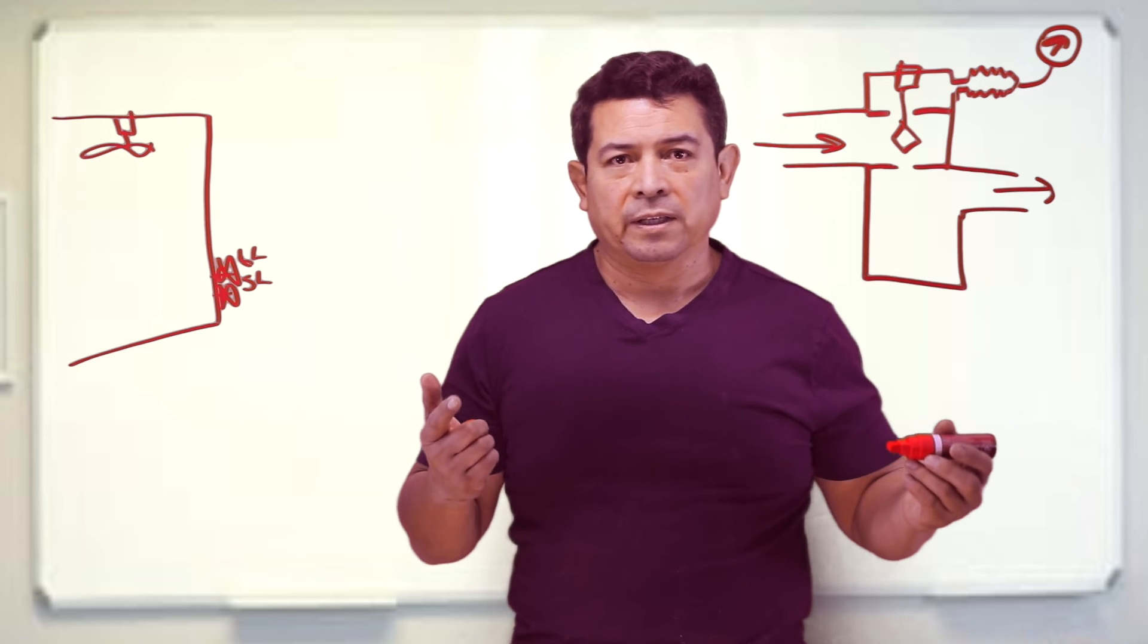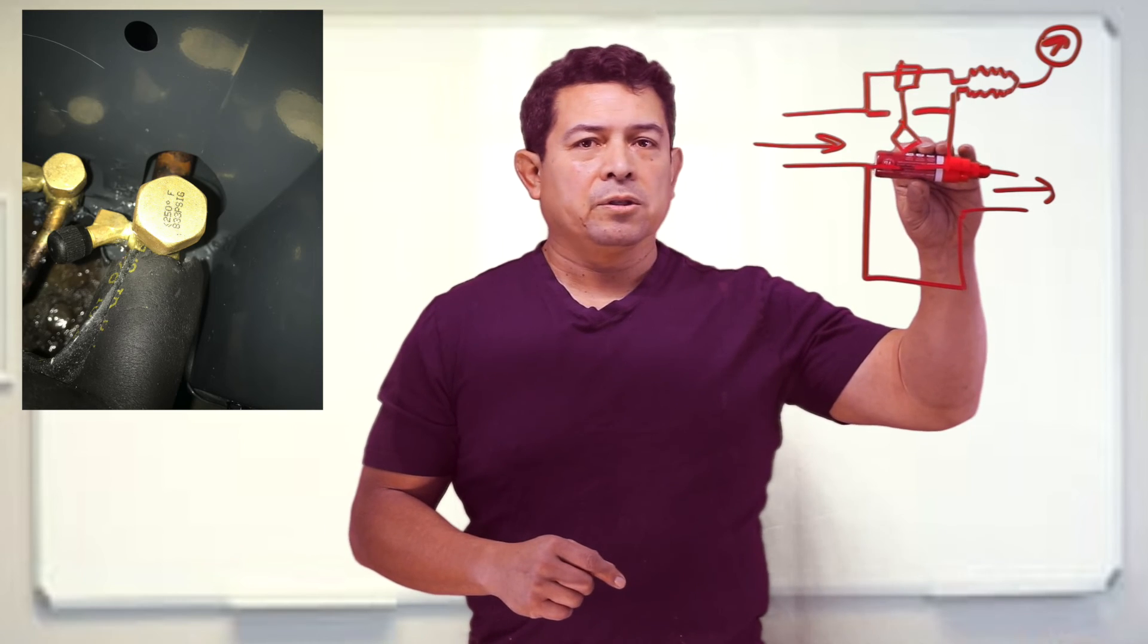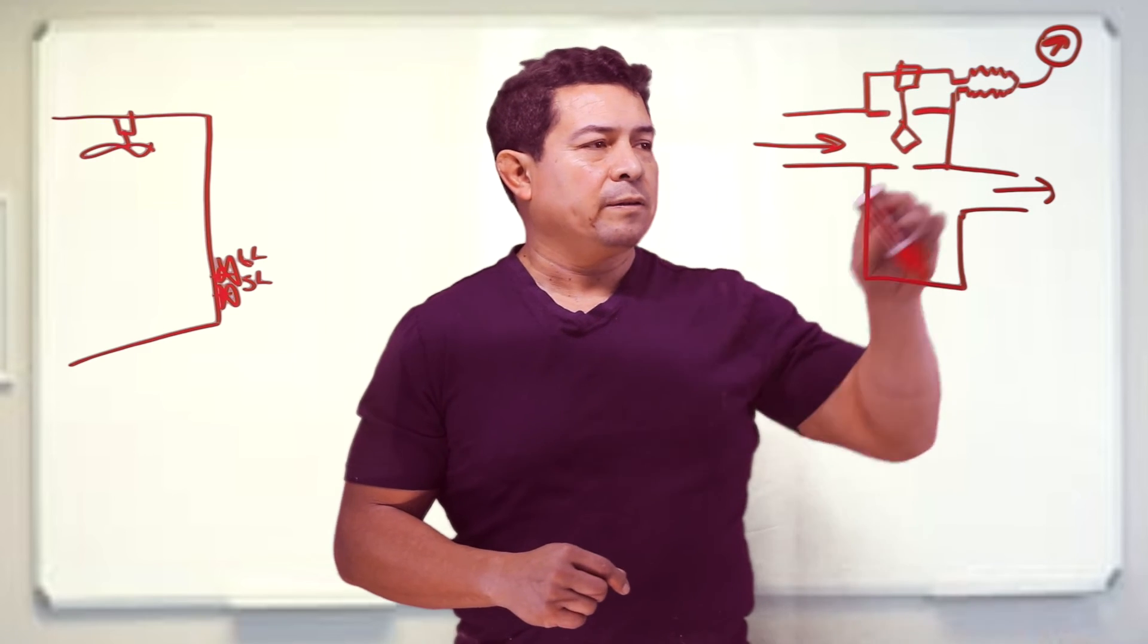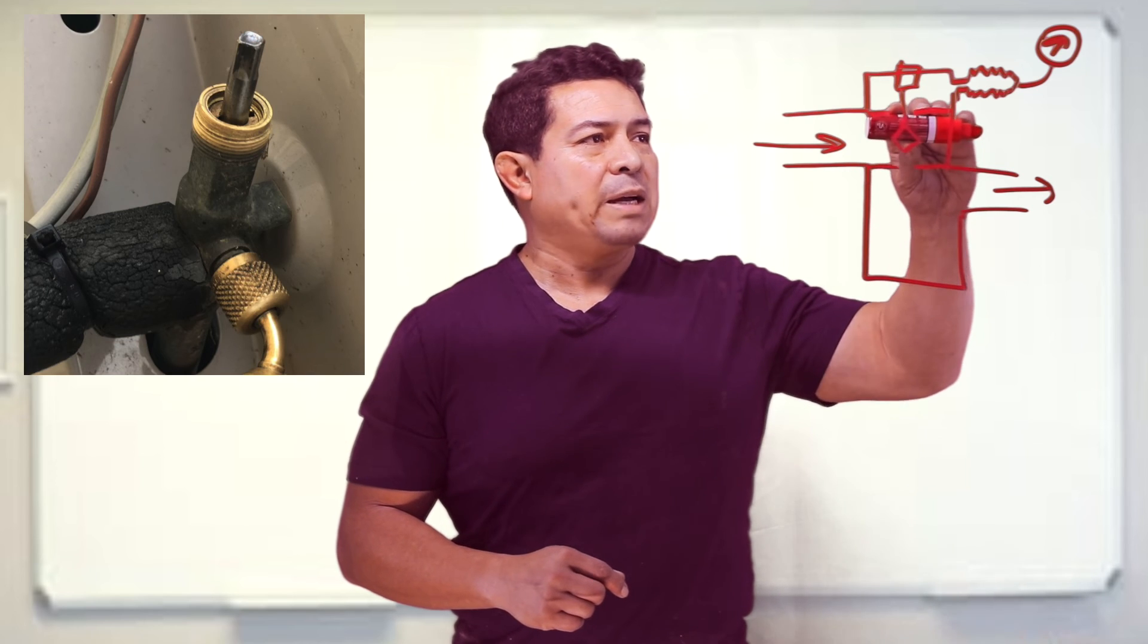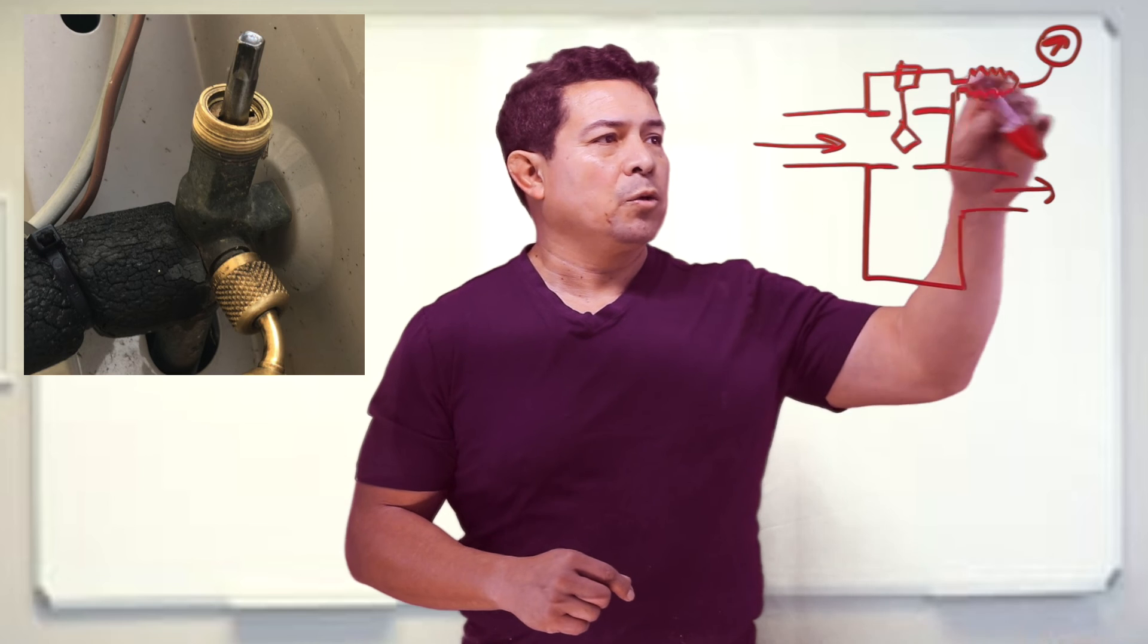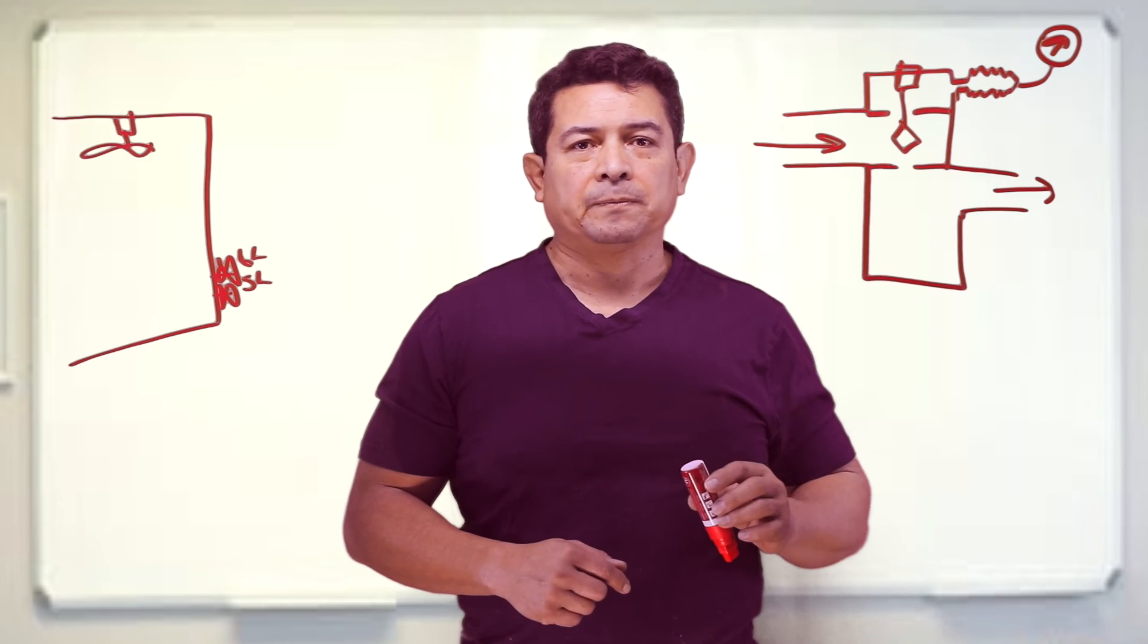So now you have the two different kinds: the one that has only two positions, fully closed or fully open, and then you have this kind that has the three position, front seated, back seated, and then throttled or mid position so we can add refrigerant, we can take pressure readings and service the system.